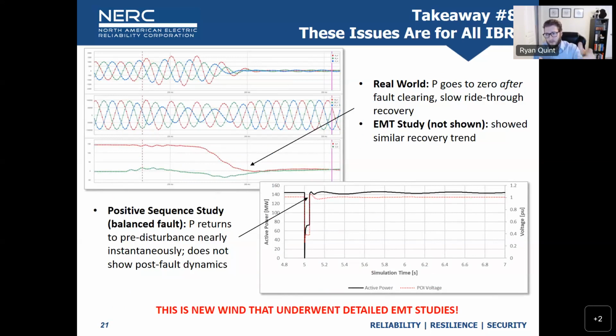Here's a good example from the Panhandle Wind Disturbance Report we published earlier this year. The top plot shows high-speed oscillography data at the POI. In the real world, when the fault occurs, power goes to zero after fault clearing. You see current go up, voltage go down, a single line to ground fault. After fault clearing, once voltage recovers, power drops to zero out of the wind plant and slowly recovers over a few hundred milliseconds.